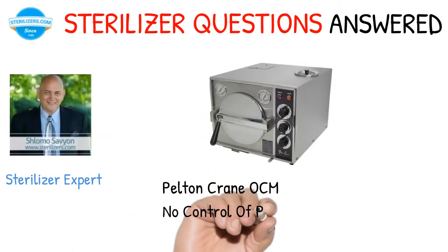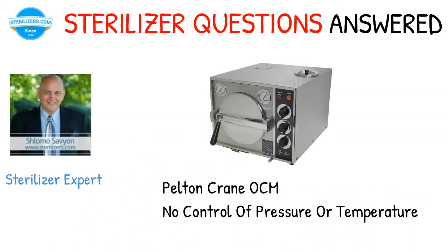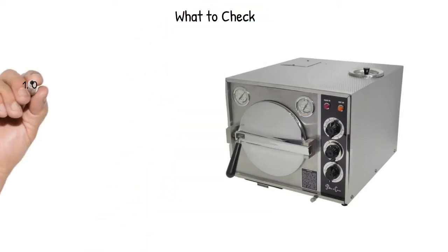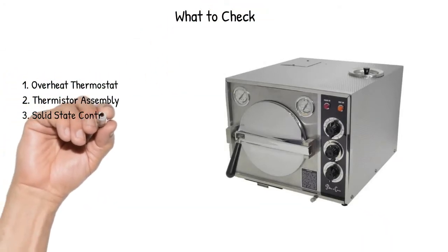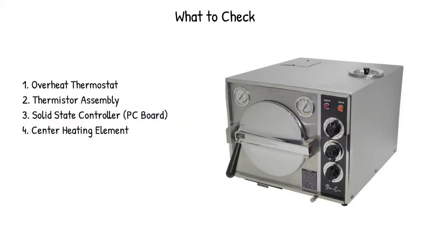Pelton Crane OCM No Control of Pressure or Temperature. What to Check: 1. Overheat Thermostat, 2. Thermistor Assembly, 3. Solid State Controller PC Board, 4. Center Heating Element.